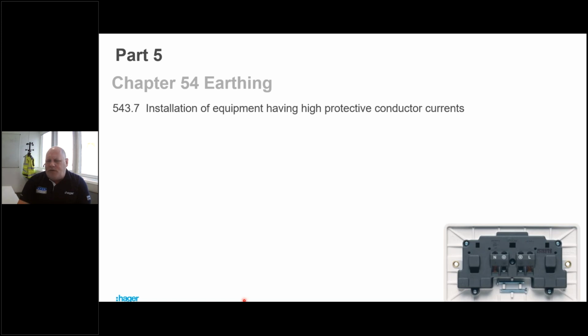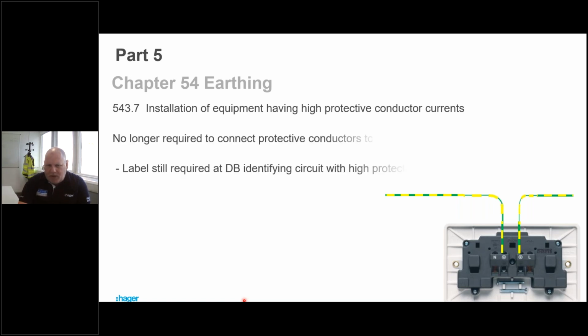Okay, chapter 54, earthing. Installation of equipment having high protective conductor currents. We've always wired sockets where we've got this kind of circuit, where we use the 2 earthing conductors on the back of a socket. Now, that's great, but there were certain manufacturers that only gave 1 earthing point on the back of the socket. That sort of excluded them from being used in this situation. They've now said we don't have that requirement anymore. We are allowed to use 1 earth terminal on the back of a socket.